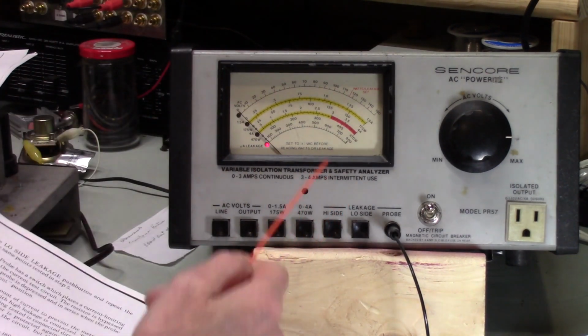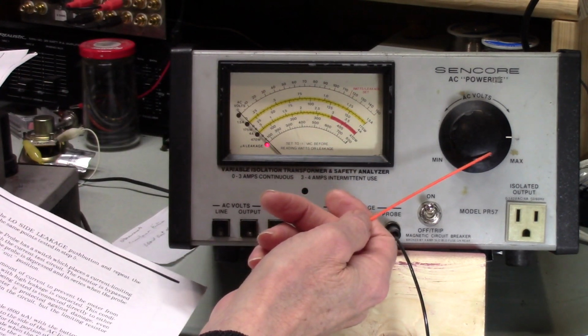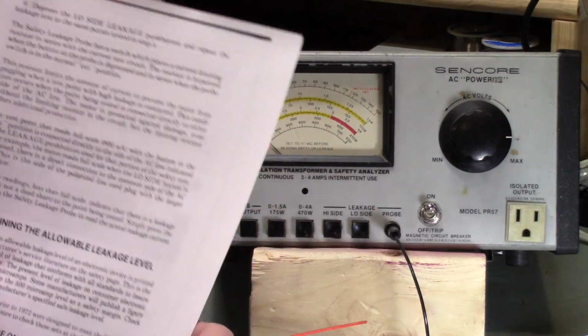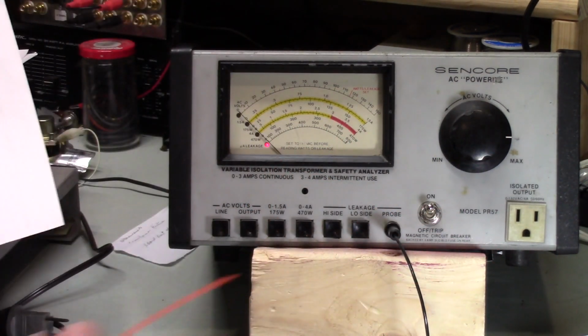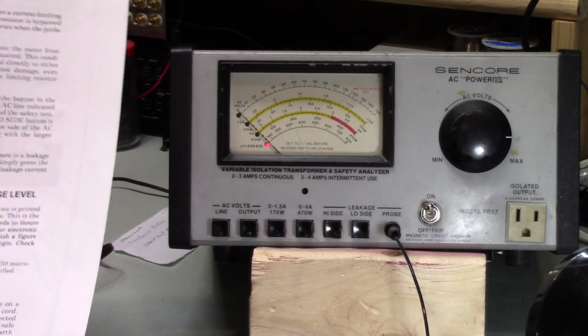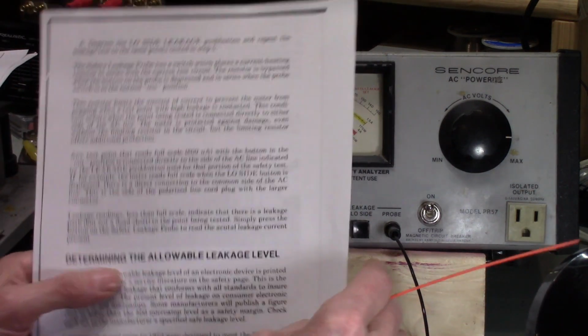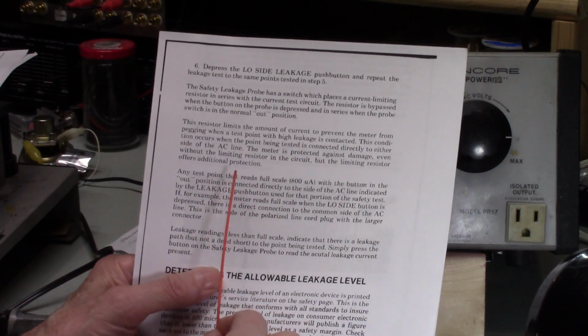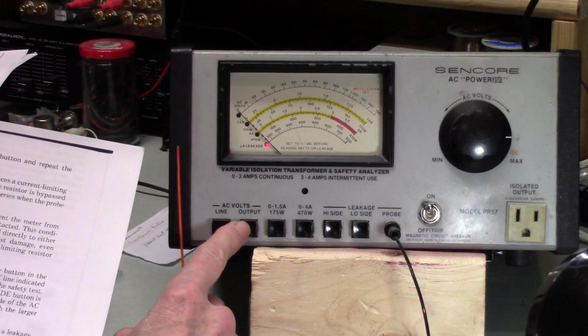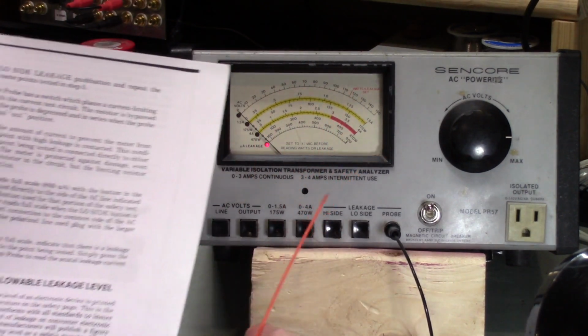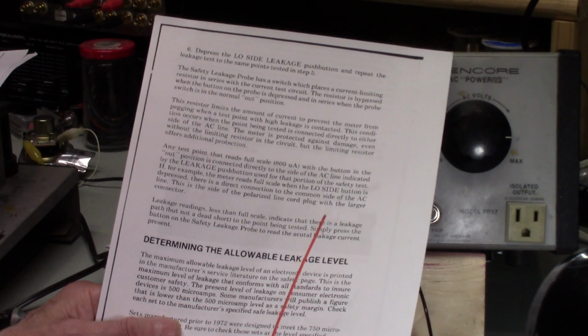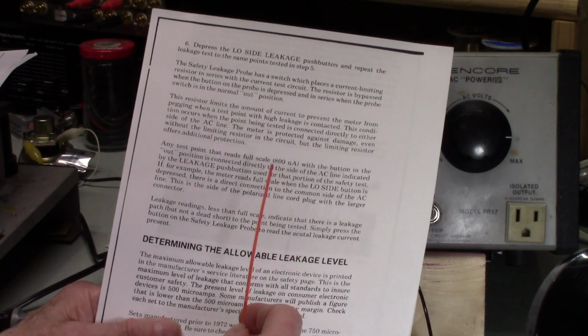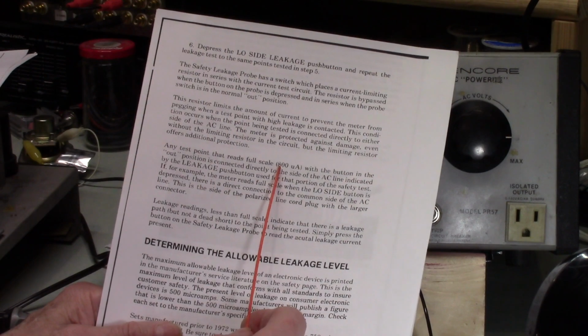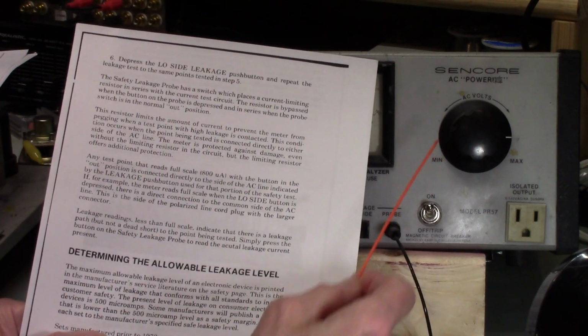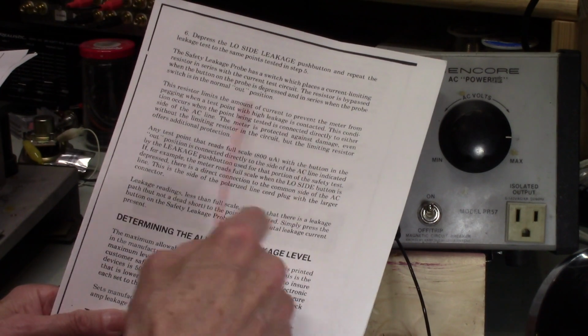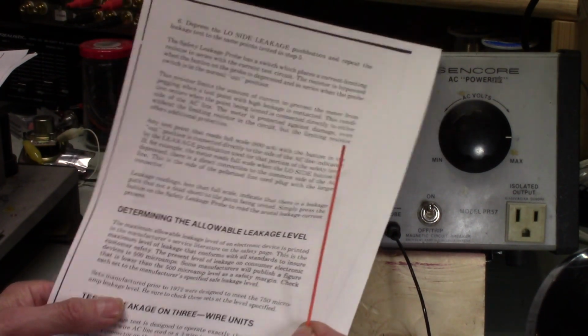The only way you're going to get 800 microamps is if this is set at 120 volts or higher. But since this stops at 800, setting this to 120 is probably as high as you want to go. So this is where I disagree - they don't tell you to go back to your output, set it to 120, and then go to the high side and check. They don't tell you to do that. But there's no way you're going to get an 800 microamp reading if this is not set to 120. Not going to happen. So these instructions seem to be a bit lacking.